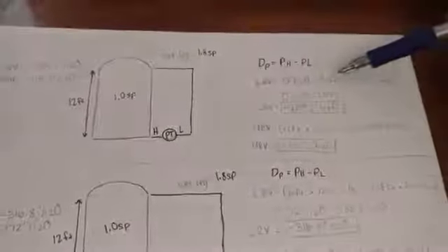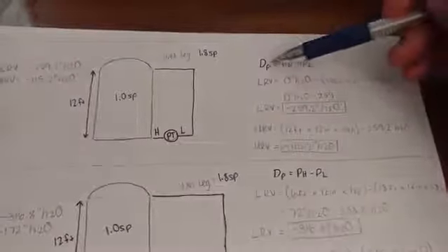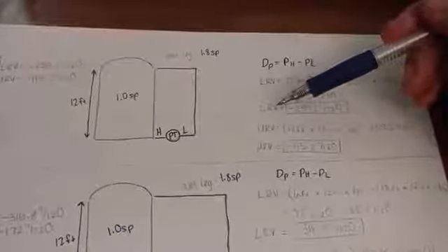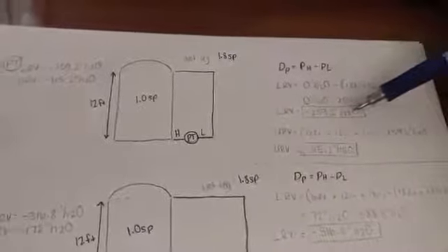And in order to do that, we're going to use 12 feet of water times 12 inches times 1.8 because of the specific gravity of this wet leg. Now we have the hydrostatic pressure for our pressure low side. And once we use this formula, we're going to find the differential pressure, and that's going to give us our lower range value, which is going to be negative 259.2 inches H2O.